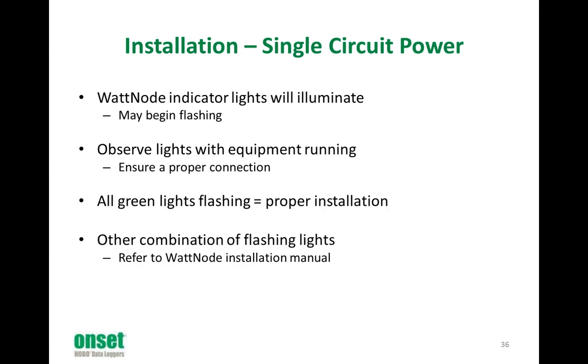So basically, for single circuit power, the WattNode indicator lights will illuminate. They may begin flashing, and you want to observe the lights with the equipment running to ensure a proper connection. If all green lights are flashing, then you've done a good job and that's a proper installation. There are cases where red lights or yellow lights will flash, and you should refer to the WattNode installation manual to help troubleshoot what those lights indicate.